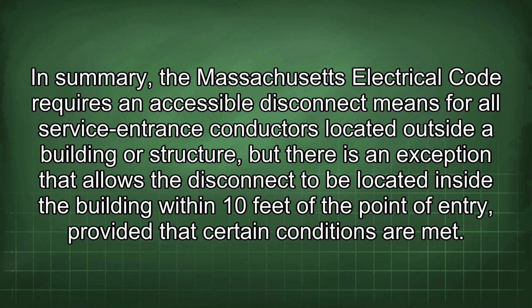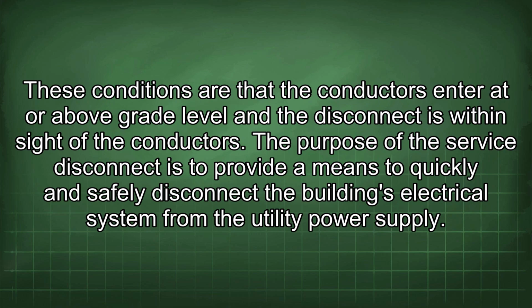In summary, the Massachusetts Electrical Code requires an accessible disconnect means for all service entrance conductors located outside a building or structure, but there is an exception that allows the disconnect to be located inside the building within 10 feet of the point of entry, provided that certain conditions are met. These conditions are that the conductors enter at or above grade level and the disconnect is within sight of the conductors. The purpose of the service disconnect is to provide a means to quickly and safely disconnect the building's electrical system from the utility power supply.